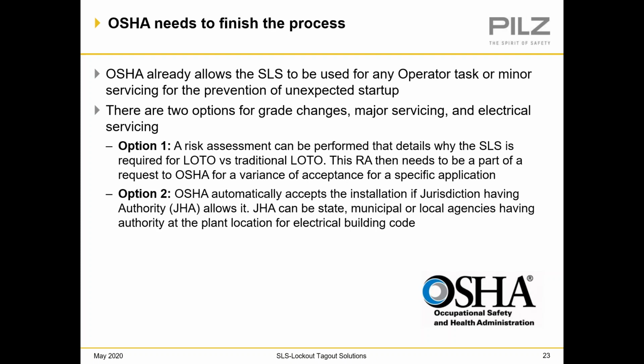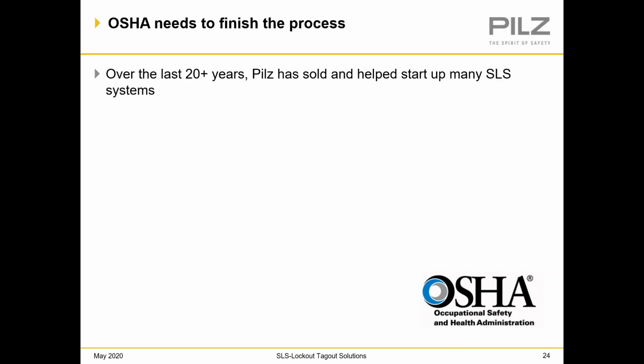One, a risk assessment can be performed that details why the SLS is required for lockout versus traditional LOTO. The risk assessment then needs to be part of a request to OSHA for a variance of acceptance for a specific application. And then option two, OSHA automatically accepts the installation of a jurisdiction having authority, JHA. JHA can be a state, municipal, or local agency having authority at the plant location for electrical building code. So those are the options for having OSHA sign off on using the SLS as a lockout device currently. And then they'll be upgraded once this newer solution is completed with OSHA, which won't take too much more time, hopefully.